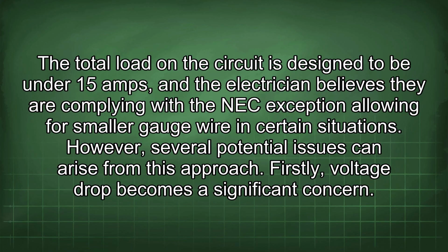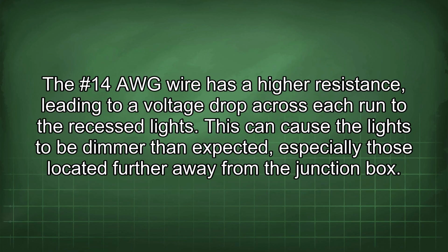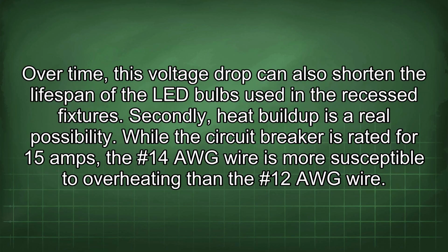However, several potential issues can arise from this approach. Firstly, voltage drop becomes a significant concern. The #14 AWG wire has a higher resistance, leading to a voltage drop across each run to the recessed lights. This can cause the lights to be dimmer than expected, especially those located further away from the junction box. Over time, this voltage drop can also shorten the lifespan of the LED bulbs used in the recessed fixtures.